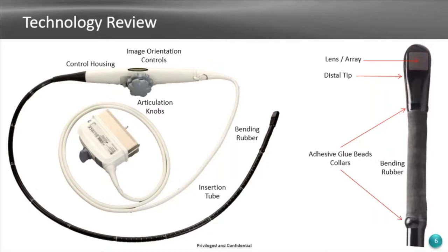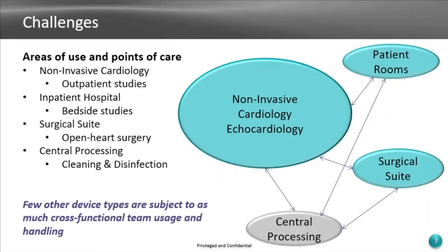Because these probes and endocavity probes are subjected to very harsh environments for cleaning and disinfecting, you've got to make sure the adhesives and other materials you're using are compatible with the OEM cleaners and disinfectants. So where are these things used? Typically in non-invasive cardiology. They can be used in patient rooms, the surgical suite, and they're also cleaned in central processing.